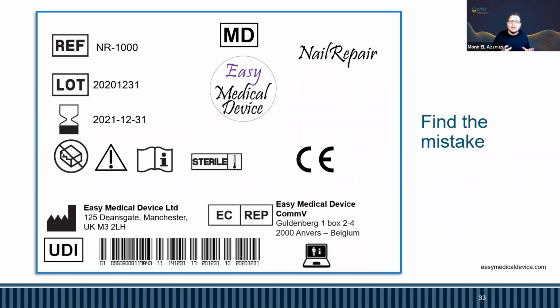So this is mainly the thing that you can also catch as a regulator or as people. When you look at a label, if you see no notified body number, that normally means it's a class 1. But if you see a sterile symbol or any symbol that shows that there is a sterilization on the product, then you say, okay, there is a mistake here. Your product is wrong. Do you have a CE certificate for your products? And this is how you can also catch some mistakes here.